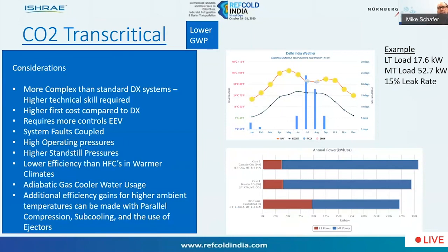Another consideration would be system faults. So if you had a system fault, because they're connected, you're likely to affect the entire refrigeration system of the store. So CO2 operates at high operating pressures, and therefore, in the event of a power outage, it has a higher standstill pressure. So there may be requirements to do some auxiliary cooling in the event of a power outage.